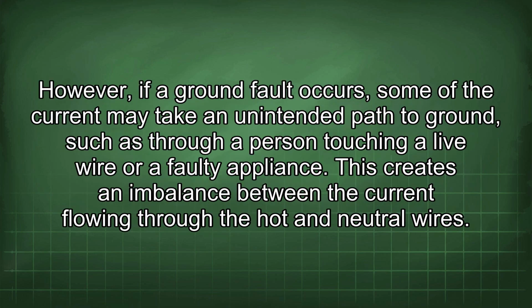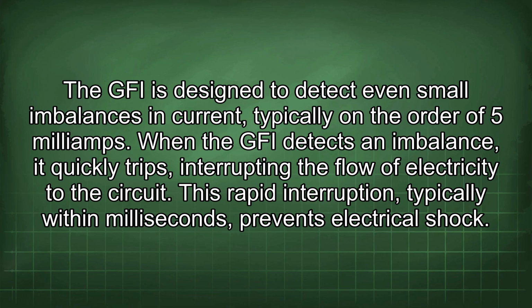However, if a ground fault occurs, some of the current may take an unintended path to ground, such as through a person touching a live wire or a faulty appliance. This creates an imbalance between the current flowing through the hot and neutral wires. The GFI is designed to detect even small imbalances in current, typically in the order of 5 mA. When the GFI detects an imbalance, it quickly trips, interrupting the flow of electricity to the circuit. This rapid interruption, typically within milliseconds, prevents electrical shock.